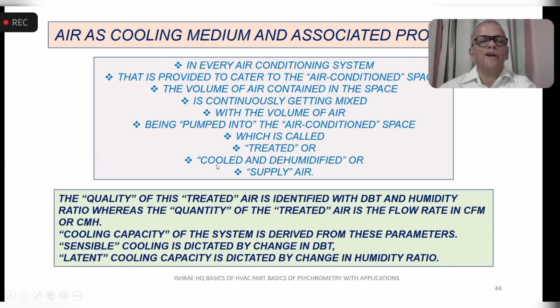When we say cooled and dehumidified, this is your air conditioning process, and you are determining from the room design condition and the sensible heat factor, and assuming the coil efficiency, what should be the ideal supply air point. The quality of the treated air is identified with the dry bulb temperature and humidity ratio, whereas the quantity of the treated air is the flow rate in CFM or CMH. The cooling capacity of the system is derived from these parameters listed above. The sensible cooling is dictated by the change in dry bulb, and latent cooling is dictated by the change in humidity ratio.